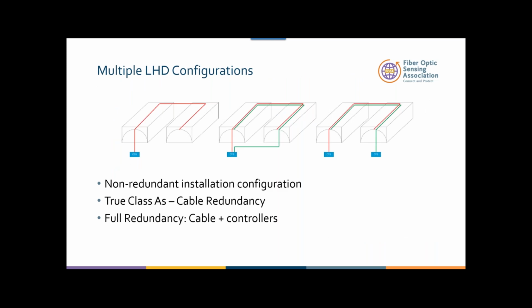The next advantage is the ability to have different configurations. One of the best configurations of the fiber optic linear detection is, for example, a tunnel, where you can have a system installed in such a way that you can monitor both lanes of a tunnel, as the first picture on the left shows. The same cable will have two fibers. One within the cable is green, one of them is red, and you can actually monitor both of them. One of them will be in channel number 1, one of them will be in channel number 2.